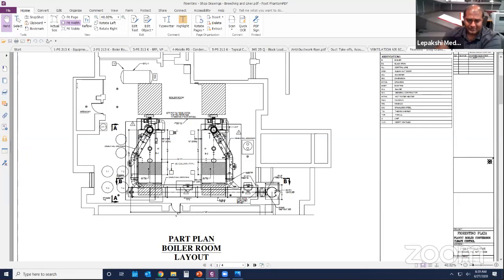The natural process happening here is called draft. What draft means is, whenever air gets heated up, its density becomes low, and cold air has more density. So the cold air in this room pushes the hot flue gases outside—that natural phenomenon is called draft.